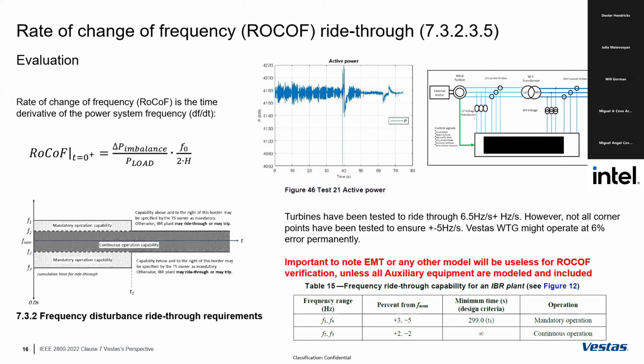So it's very important to understand the way we are going to evaluate the ROCOF. If we evaluate ROCOF on a converter level, we might get a false positive that we can ride through when, in comparison, we evaluate it on the field. And on top of this, to add some more complexity, it is very difficult, near to impossible, to create an event that can evaluate ROCOF on the field. So we might rely on simulations, but the reality is that most of the simulation models do not contain the auxiliary systems. So if I test ROCOF in a PSCAD model that I have the impression is super accurate, it might not give me the reality of what the ROCOF capabilities of the technology are.